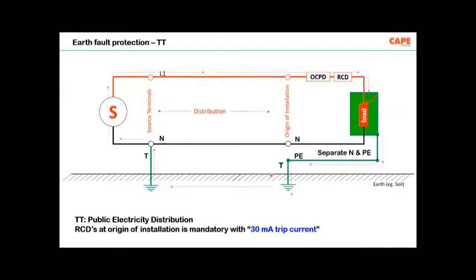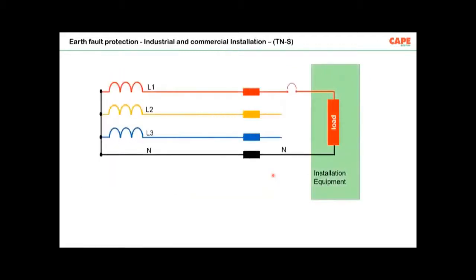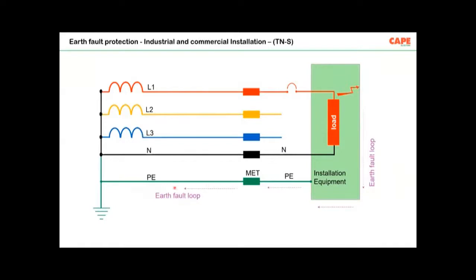Now, remember, this TT is only for public electricity distribution, not for industrial or commercial installations, or places where you have a transformer within your compound, or if you are an HT consumer; this is not applicable. For high-rise buildings, for industrial and commercial installations, we are supposed to have a network called TN-S, which is basically a 5-wire system. In a TN-S system, imagine there is a fault. The fault return is happening through the protective conductor, and this is the way the fault loop works. The dotted lines show the fault loop circuit.